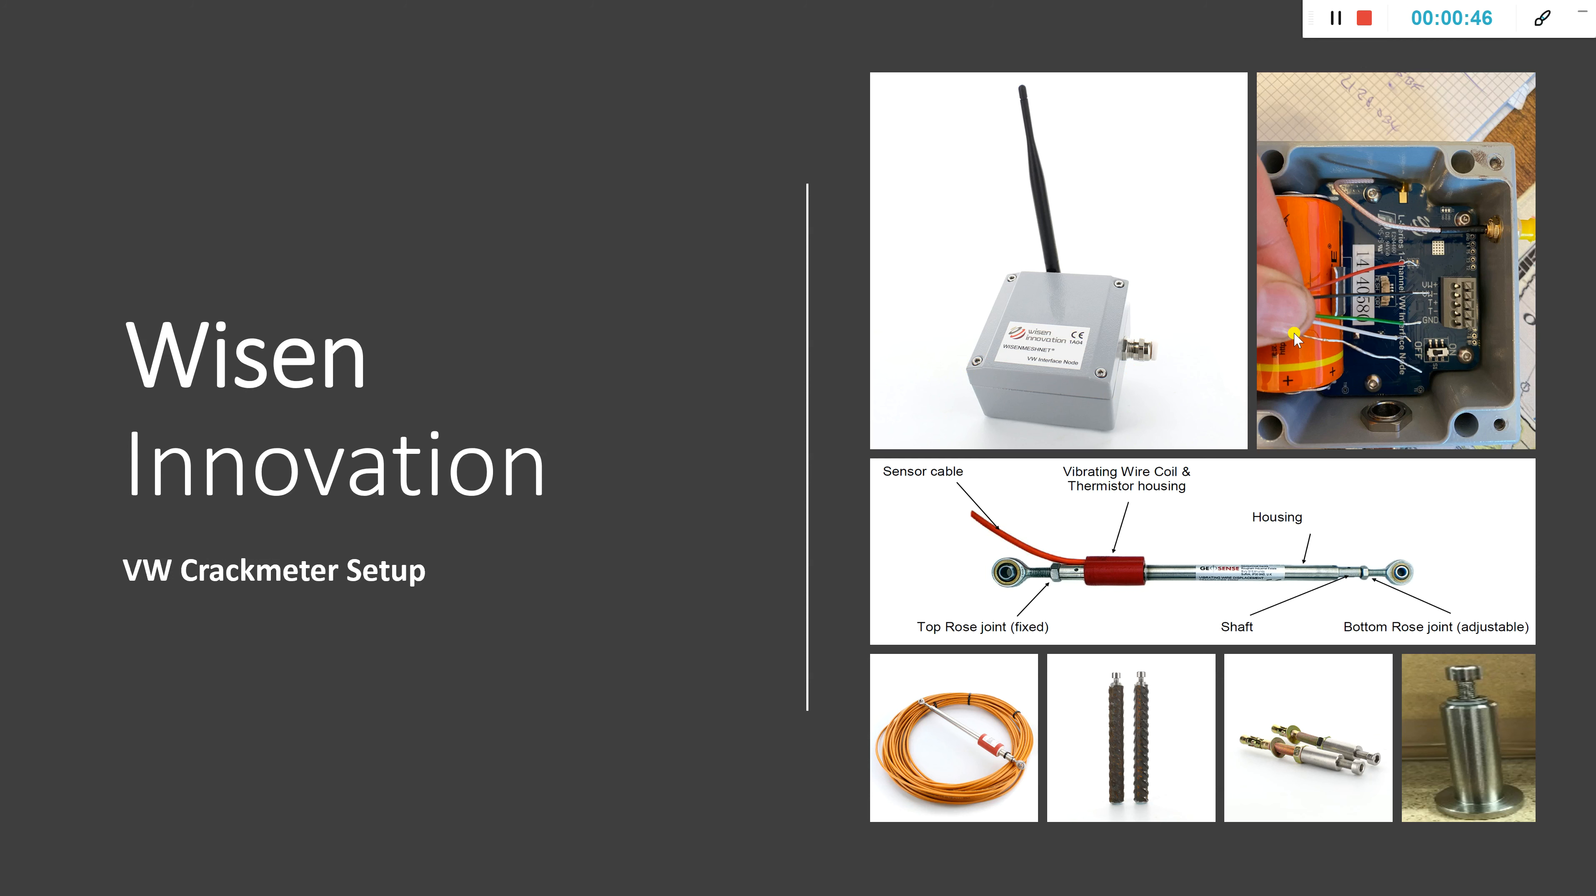In terms of the node itself, you can see here there are connection ports associated to the wiring from the actual crack meter. If we review the color coding aspect, red is VW plus, black is VW minus, green is T plus, white is T minus, and the silver strand at the bottom is a ground cable. These might be wired up and delivered to you direct from Wisen or you might look to wire these yourselves.